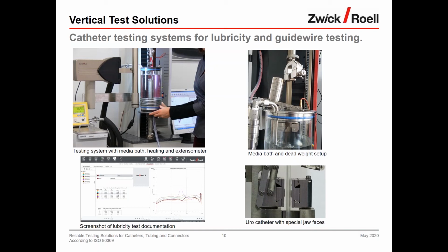I also want to emphasize that the gripping unit is equipped with dead weights, which are key for reproducible and reliable test results. The system can easily be adapted to different catheter types with exchangeable jaw faces that show individual gripping capabilities. That makes the system flexible and reproducible. Cyclic loading of the catheter also simulates the insertion process.